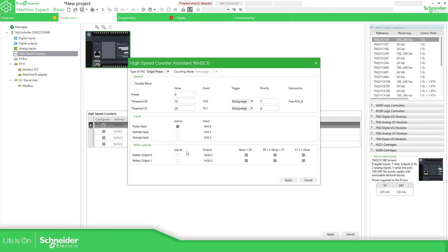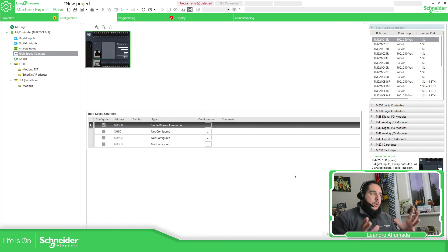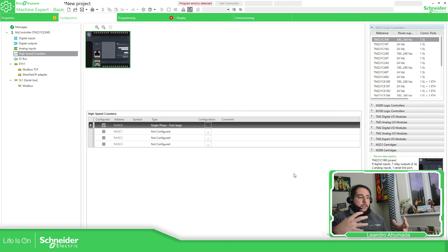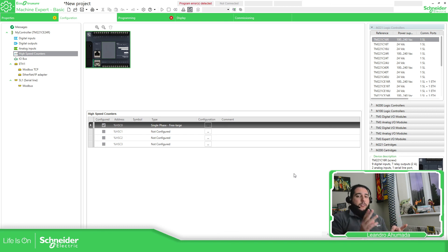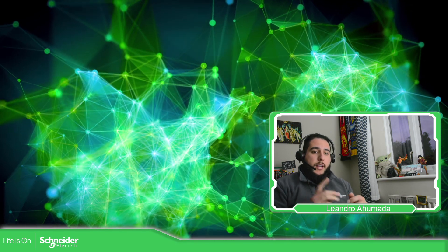For the reflex output, you can specify whether to use it, and if so you define the assignation — which output to activate based on the configured threshold. The same applies for reflex output two. This has been an overview of the high-speed counter: the idea is to use it when you have an encoder or a signal with pulses up to 100 kHz. We will cover single phase, different encoder configurations, and the frequency meter in more detail later. Thank you very much for watching and I'll see you in the next one.